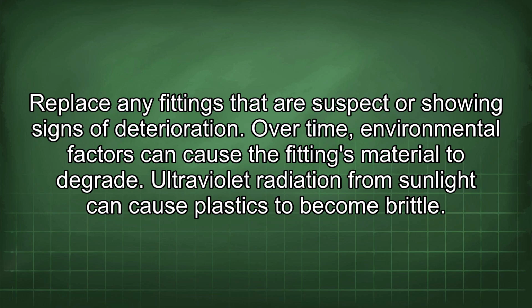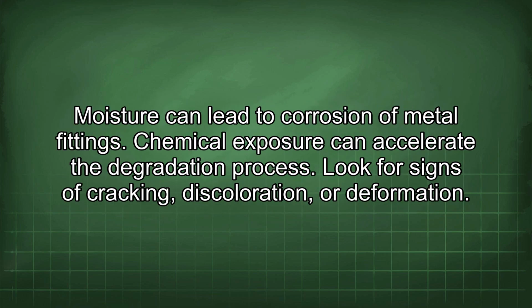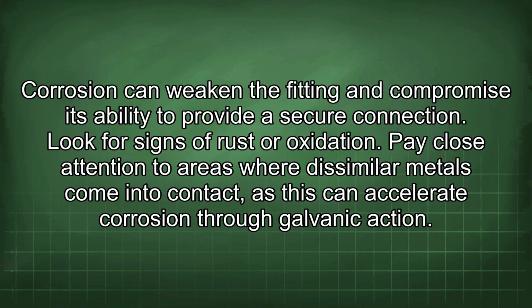Ultraviolet radiation from sunlight can cause plastics to become brittle. Moisture can lead to corrosion of metal fittings. Chemical exposure can accelerate the degradation process. Look for signs of cracking, discoloration, or deformation. Corrosion can weaken the fitting and compromise its ability to provide a secure connection. Look for signs of rust or oxidation. Pay close attention to areas where dissimilar metals come into contact, as this can accelerate corrosion through galvanic action.